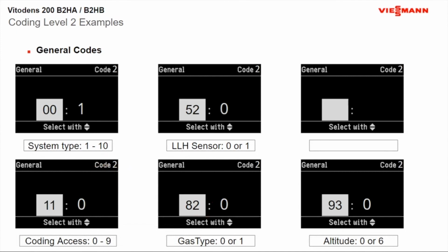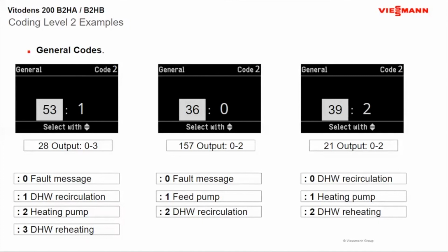If you're at higher altitudes, above 10,000 feet, there's actually a coding card change, and you can also adjust your altitude here. A lot of times that's not recommended. I would talk to tech support if you're having issues above and beyond coding card changes, because sometimes we found in some altitudes above 10,000 feet, you didn't really need the coding card. It's a fan speed change because the air is lighter, but sometimes we find it ran better without the coding card. So you'll see changes to that coming up as well.